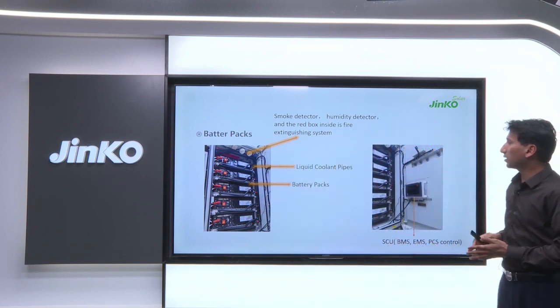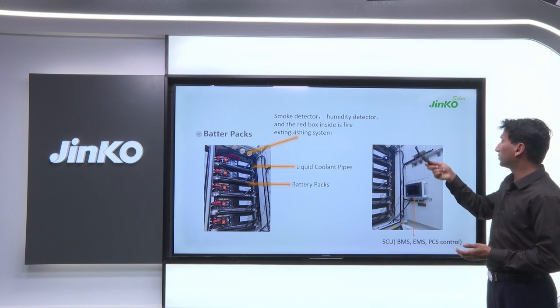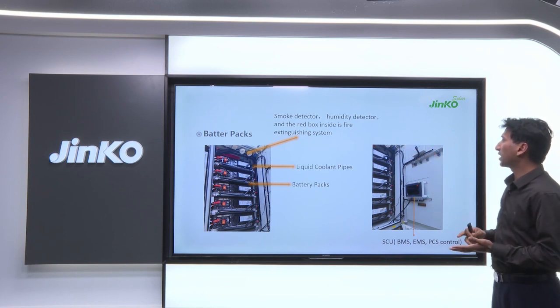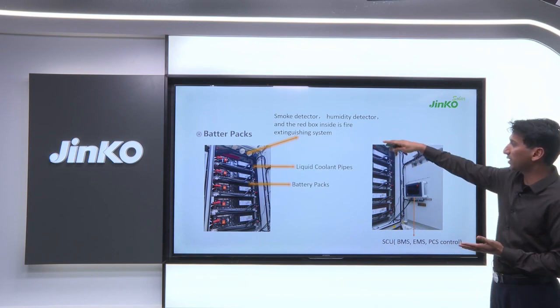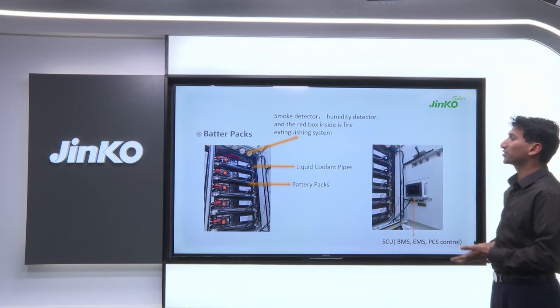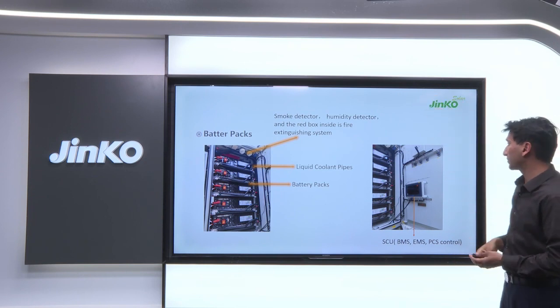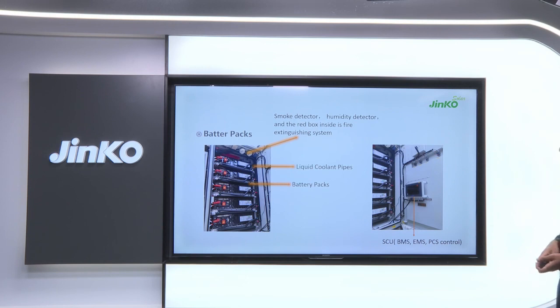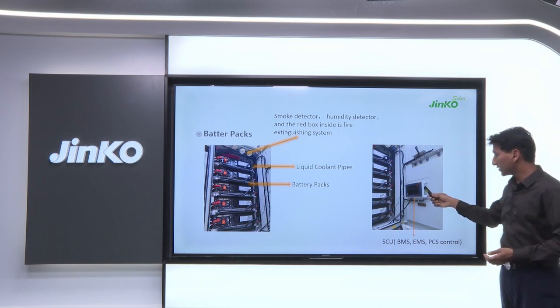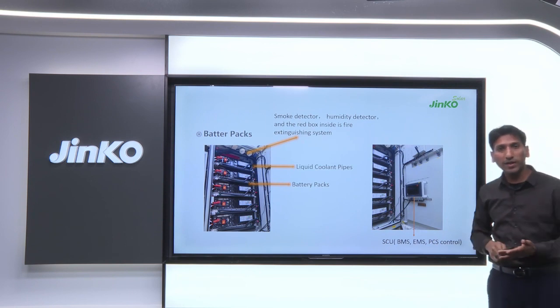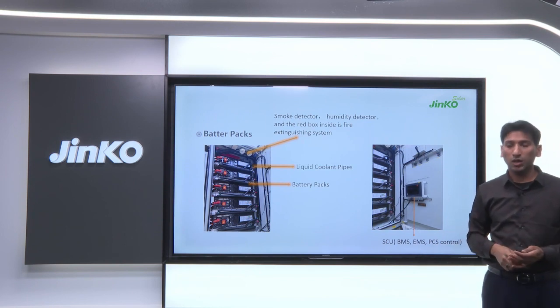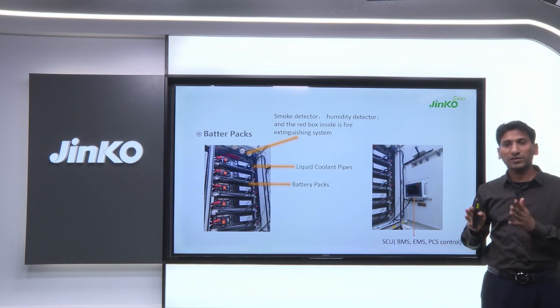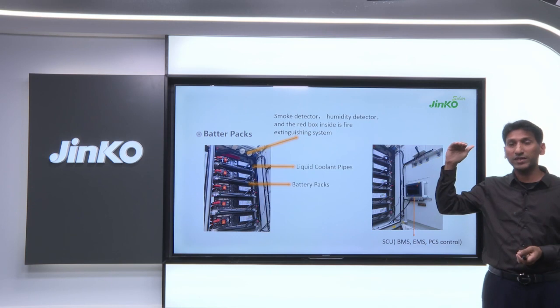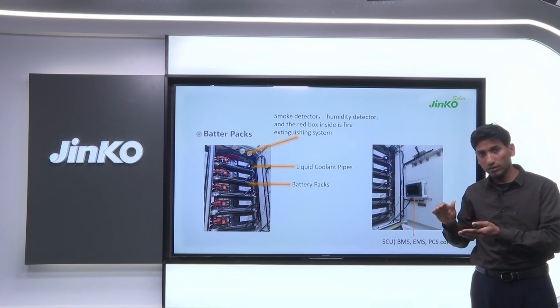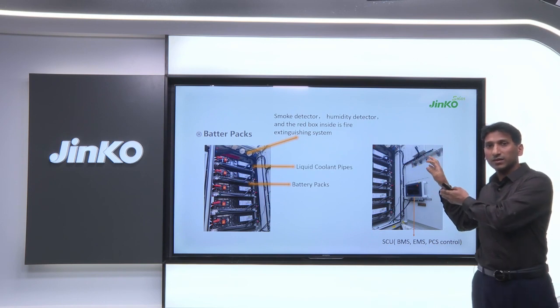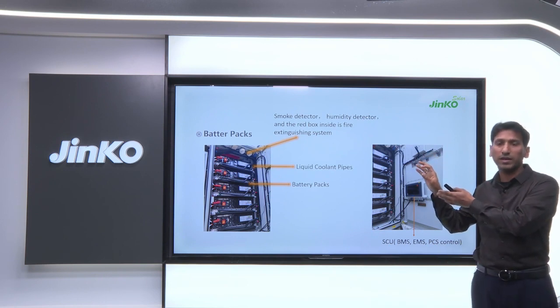In this section, you can also see the smoke detector. We have a humidity detector and a temperature detector. On the back side, that small red thing is the fire extinguishing system, which is installed there. When you open the gate of the master cabinet, you can see this screen, the HMI. If you have been installing ESS systems, you will have noticed that there are 3 layers of BMS. The first layer is in the battery pack. The second layer of the BMS is on the high voltage box, and the third is another level of BMS that connects to the PCS.